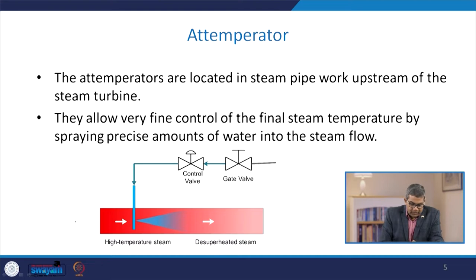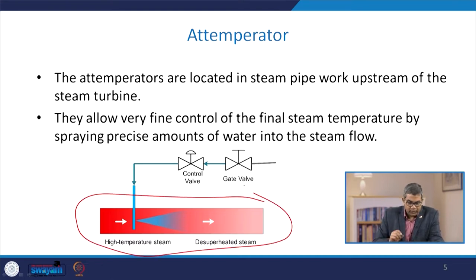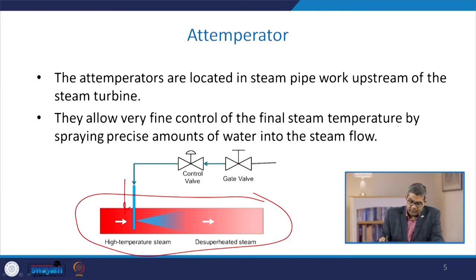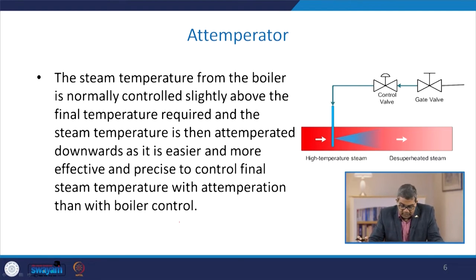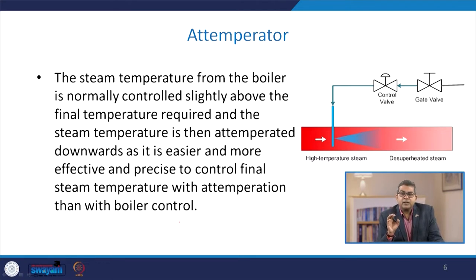Recalling from the previous lecture on reheaters, the attemperators are located in steam pipework upstream of the steam turbine. They allow very fine control of final steam temperature by spraying a precise amount of water into the steam flow. The steam temperature from the boiler is normally controlled slightly above the final temperature required, attributed to the various irreversibilities associated with the steam piping network.